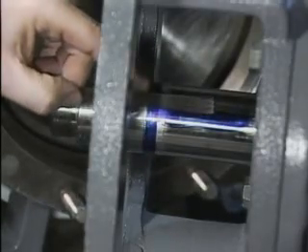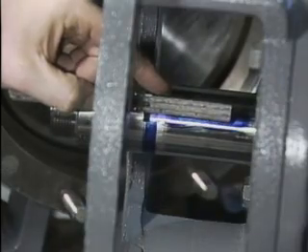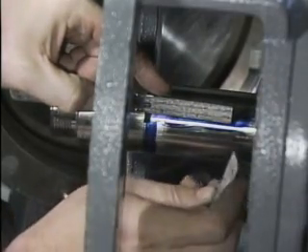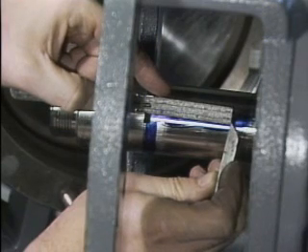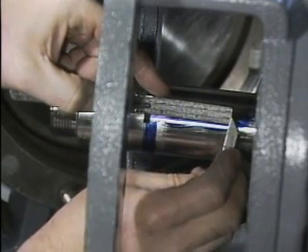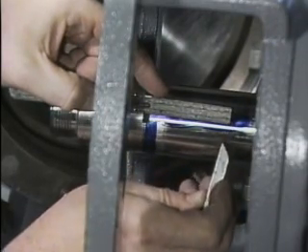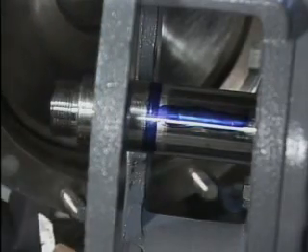Of course, there are some exceptions to the general procedures that we've just seen. For one thing, seals are not always mounted on shaft sleeves. A variation in the measurement procedure is associated with the location dimension for an outside seal. This type of seal is mounted outside the casing that's being sealed. So the second scribe line, which is used as a reference line for properly positioning the rotating ring collar, is made in the direction away from the impeller end of the shaft. Taking installation measurements is a critical first part of the procedure for installing virtually any type of mechanical seal.